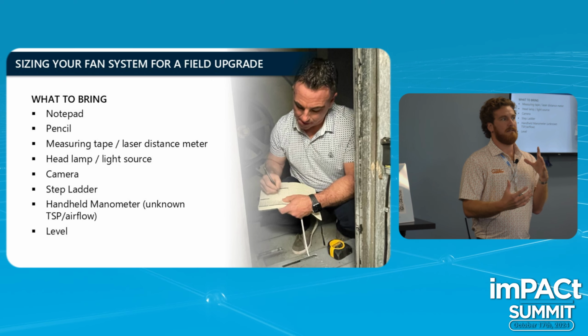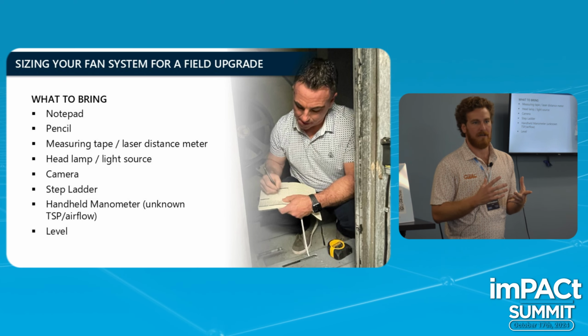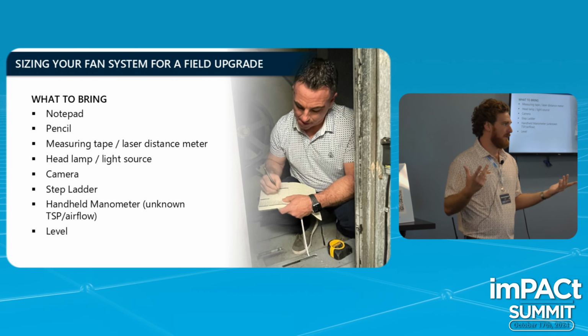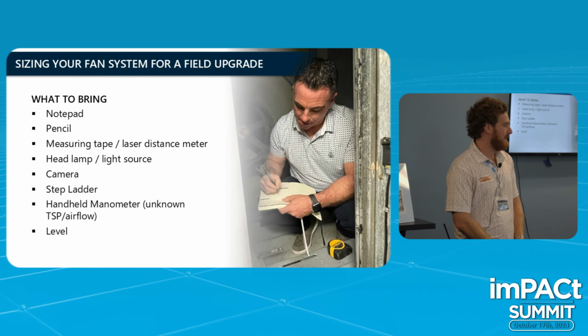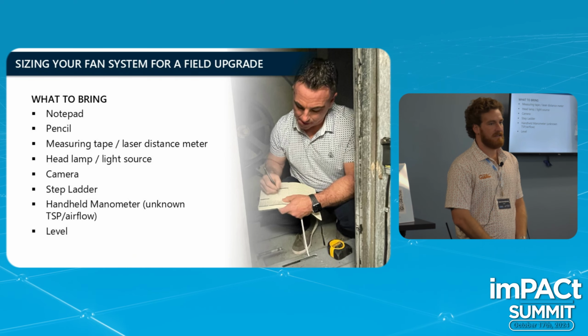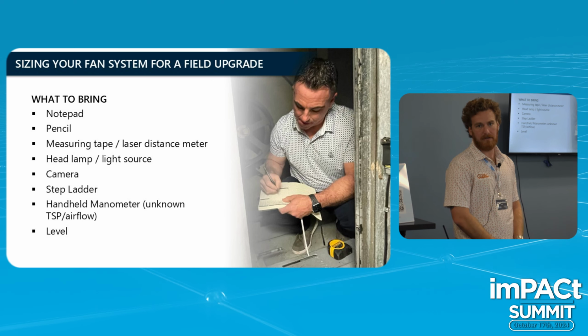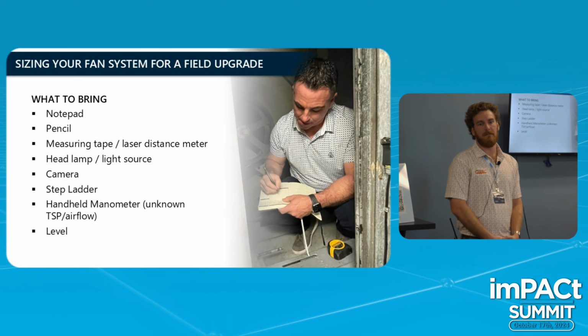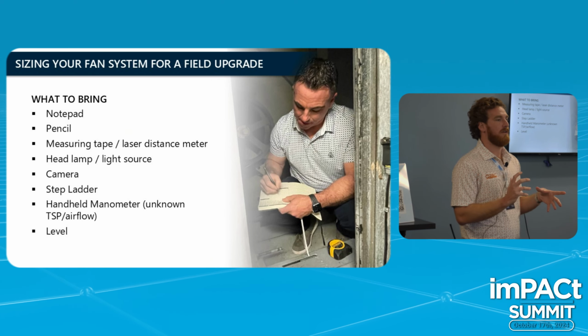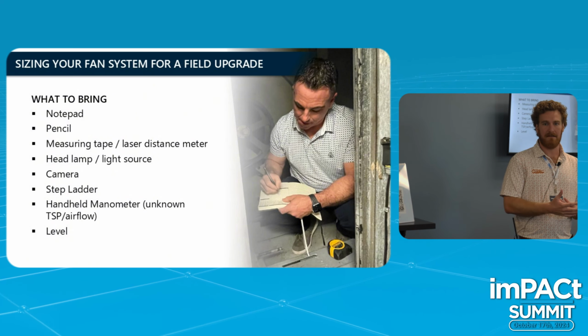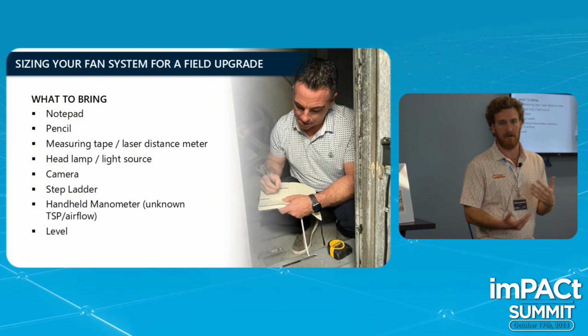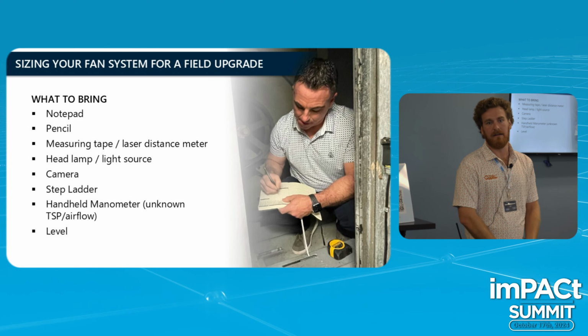As far as sizing the system goes, you'll typically have a schedule from the existing unit or some old plans. You can use the design CFM and total static pressure to get a budget going, but before we actually build the product, you want to get it more refined, so do a test and balance if one isn't already available.